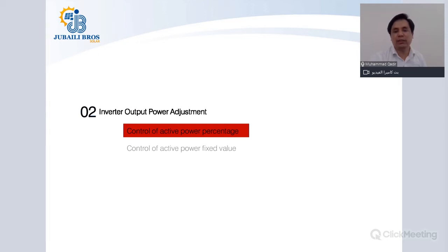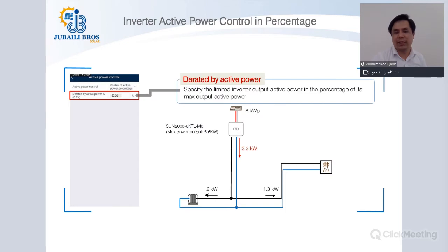The first option under fixed power limitation is the control of active power in terms of percentage. So you will put a percentage here, and let's suppose in the scenario shown on the screen, the output power is fixed up to 50%. The inverter on this PV plant is a 6 KTL-M0, which can provide a maximum of 6.6 kilowatt. Since we have configured it to give a maximum of 50% of its rated power, it is limiting its output power to 3.3 kilowatt. Although the PV capacity is high and generation could be more than this, since you want that these inverters should not provide more than 3.3 kilowatt, more than 50% of its max output power, it will limit itself to that particular output power.